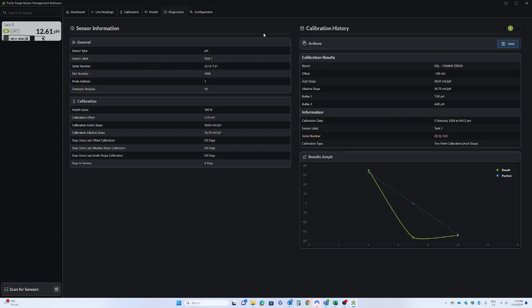This page here contains important information such as the sensor label and serial number, the part number so we know what sensor it is, the firmware revision, as well as its health score, and other information such as the offset, its previous calibration results, when it was last calibrated, and most importantly, the number of days in service. Over on the right here, we can see the results of the last calibration.